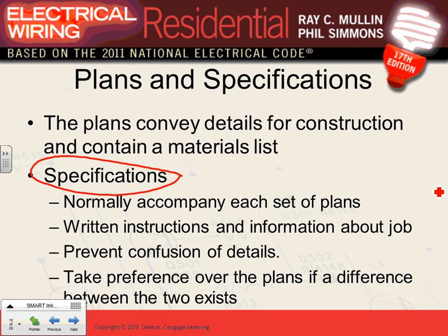Prevent confusion of the details. If there is a plans difference, usually the specification will rule. If there's a difference between the spec and the plan, spec rules. For example, in my specification I say minimum of MC cable required for this type of project. In the plans, if I say AC cable, and there's a difference, MC cable rules because the specification rules it. So we have the blueprints and the big spec together. That's your contract to do the project, and all of them are based on this or higher, based on the NEC code book or higher.